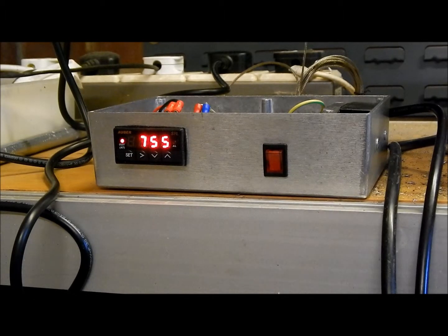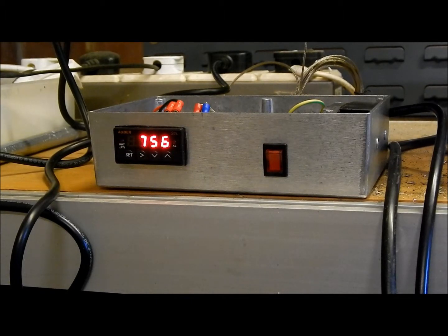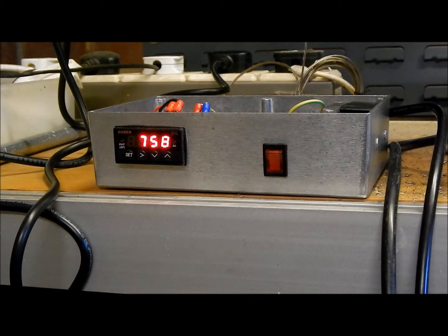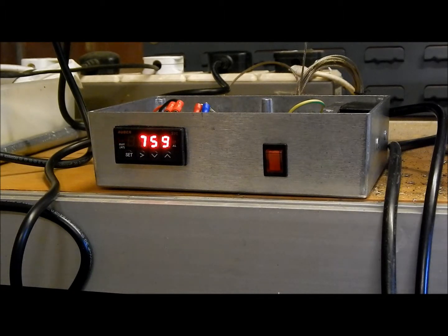It's on its second cycle now. The relay turned back on at 725 so we'll see how much it overshoots this time. The relay's turned off again so it looks like it's overshooting by about 9 degrees.